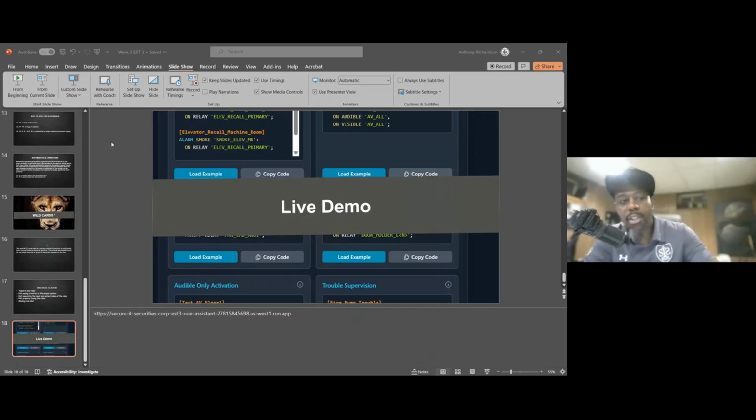So whatever devices you would want in the AND group, you would have to go inside the object configuration side. Let me just get rid of this. Go on your object configuration side, and all you will have to do is just make sure you select whatever devices you want within that list. And once you do that, you bring it over here, and now you have that in that AND group. So whatever devices are within this AND group need to perform whatever function you identified here. So I need 3 of them to go into alarm before this AND group will go true. And once 3 of those smoke detectors, let's say under the raised floor, go into alarm, then that AND group will become true.